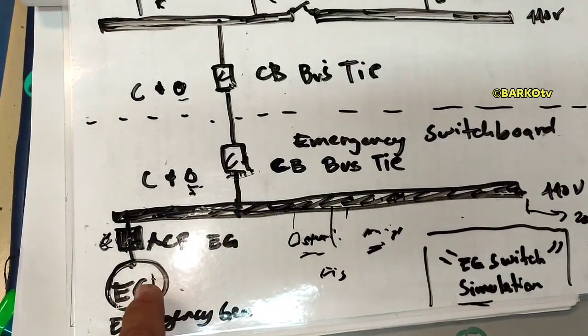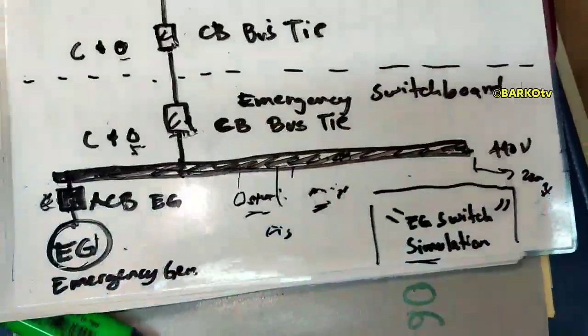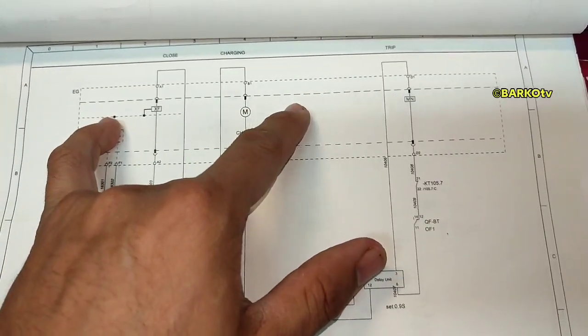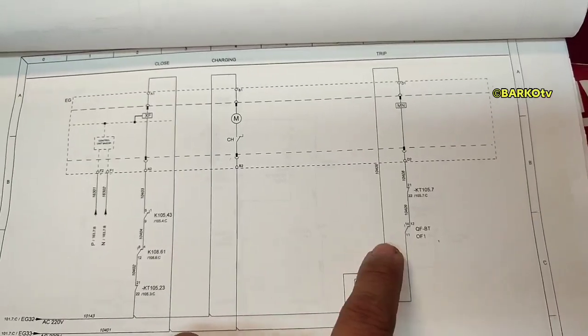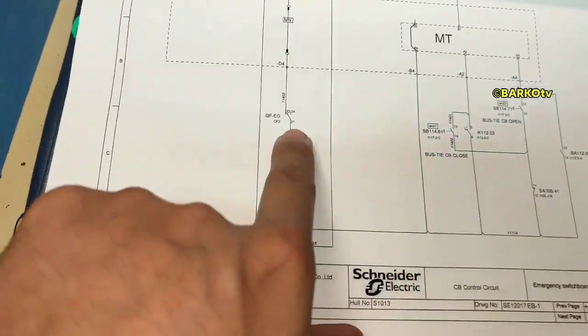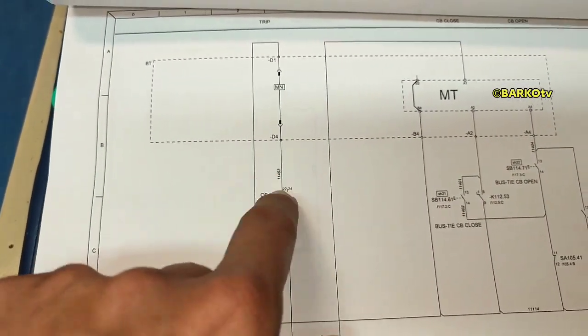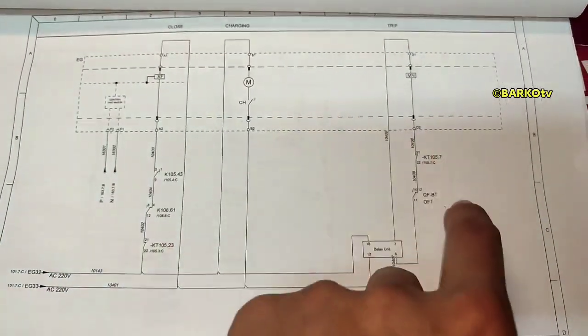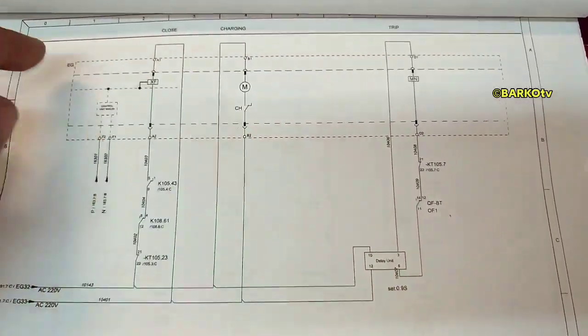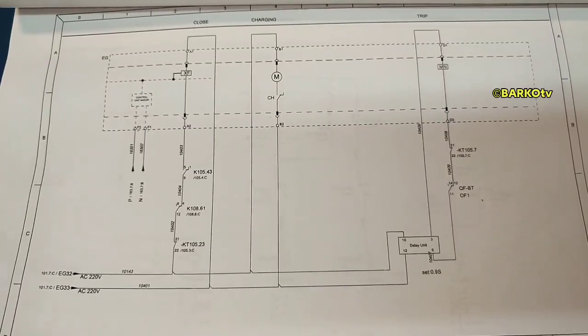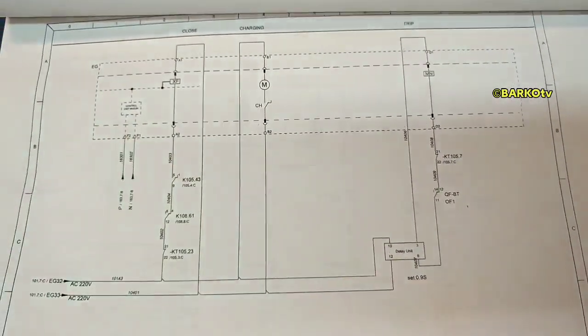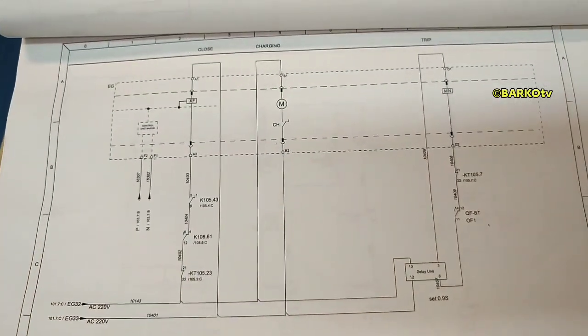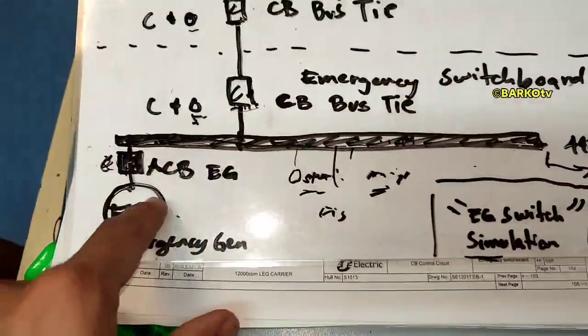These are the contacts for the bus tie. When the emergency generator ACB closes, it will also trip this bus tie — there is a contact from the emergency generator ACB that trips the bus tie. Also, there is a contact from the bus tie that trips the ACB. This is an additional safety interlock between the two ACBs — bus tie will open, the ACB for the emergency generator will later open as well. That is the interlock safety for the emergency generator.